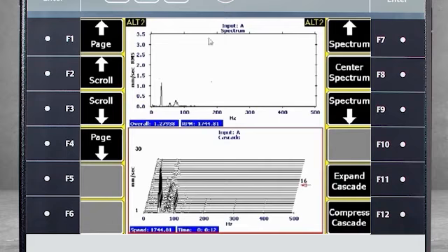If I go all the way to the last spectrum measured when the machine was at almost 0 speed, you see the imbalance value going down as well. When I go back up, you can see the measurement increasing.